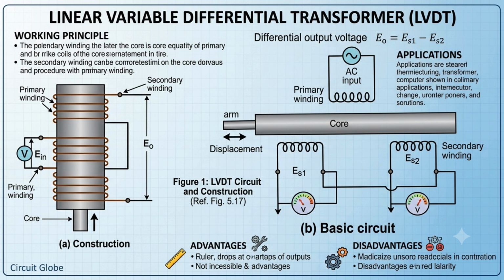Disadvantages of LVDT: larger displacements are required for differential output. They are sensitive to stray magnetic fields. Sometimes the transducer performance is affected by vibrations. The receiving instrument must be selected to operate on AC signals, or a demodulator network must be used if a DC output is required. The dynamic response is limited mechanically by the mass of the core and electrically by the frequency of the applied voltage. The frequency of the carrier should be at least 10 times the highest frequency component to be measured. Temperature affects the performance of the transducer. These are the disadvantages of LVDT.